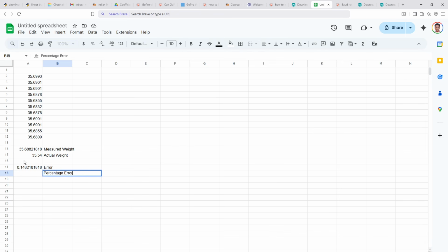this will be equal to this by 5000 into 100. 5000 is the full measurement. So you can see this is less than 0.01%. As I told you, 0.01% of error is an acceptable error when it comes to load cells. Alright, so we will stop over here.